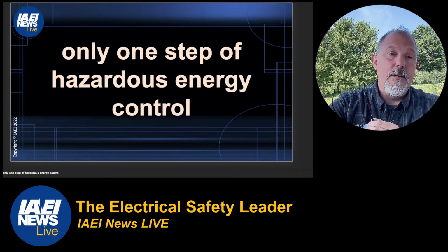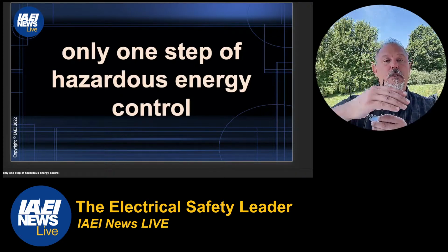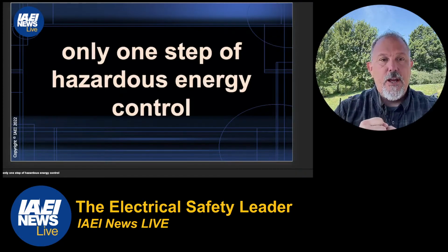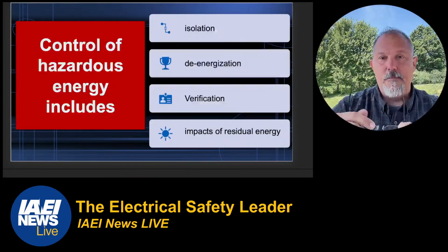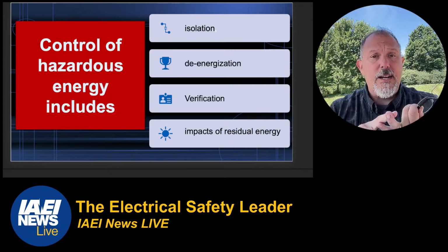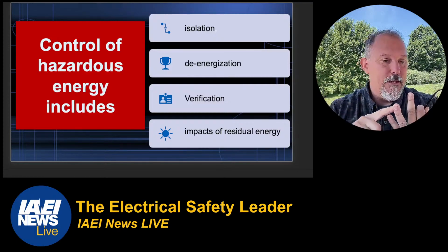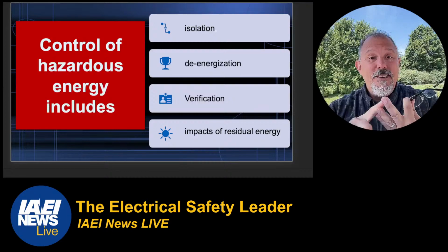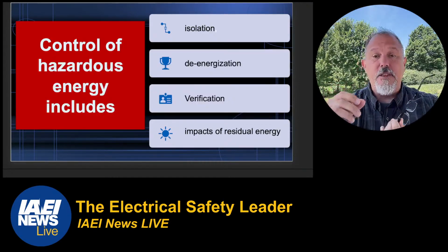So you've got to think about things with regard to likelihood and severity, right? You think about risk, and when you think about controlling the hazardous energy, it's more than just lockout tagout. You've got to isolate the issue. You've got to de-energize. De-energization obviously plays an important role when we're in the electrical industry.